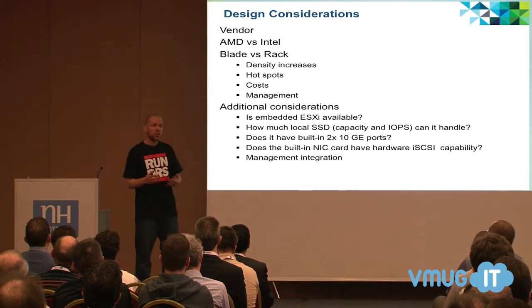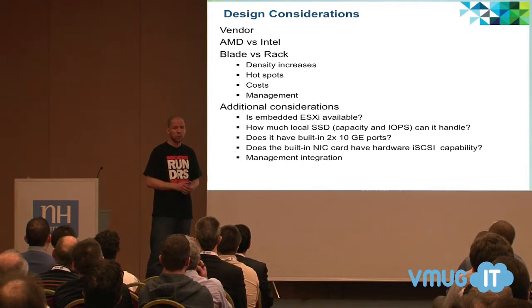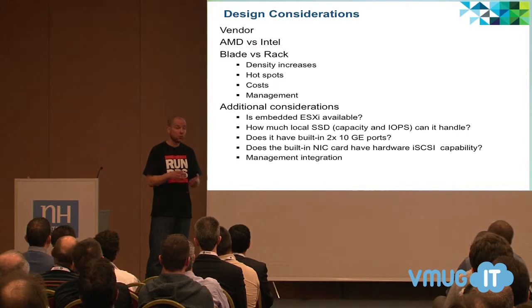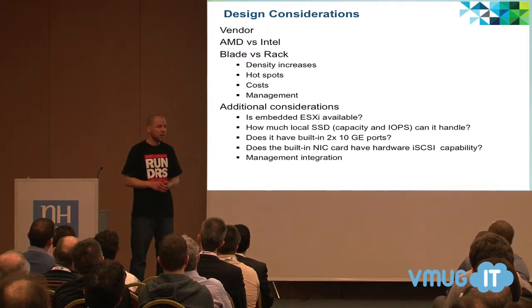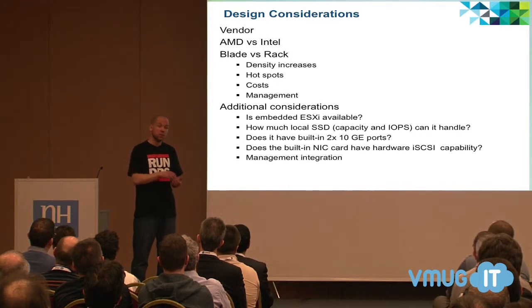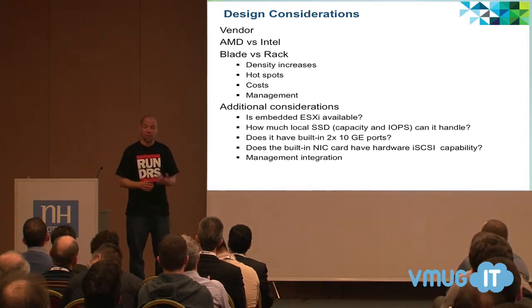Blade versus rack: a thing a lot of people forget when they start using blades is that it creates hotspots in your data center. When I did my first virtual design at an insurance company, management forced us to use blade chassis. We went from six racks of 150-200 physical machines down to two racks with four blade chassis. The cooling system couldn't handle it because the amount of hot air blown out of the blade chassis was far more significant than the 1U or 2U servers we'd replaced.